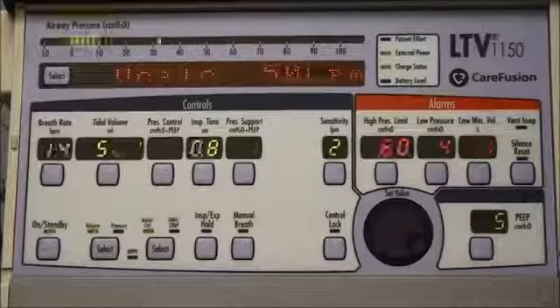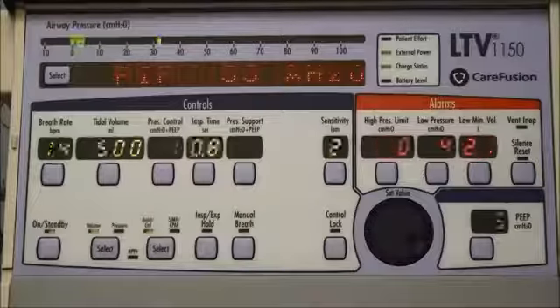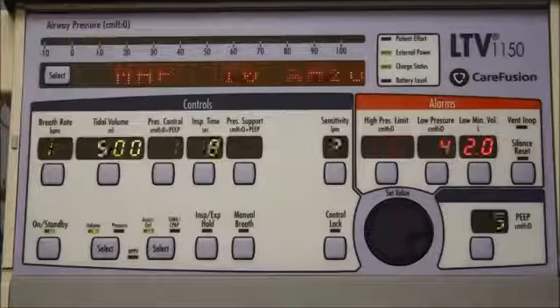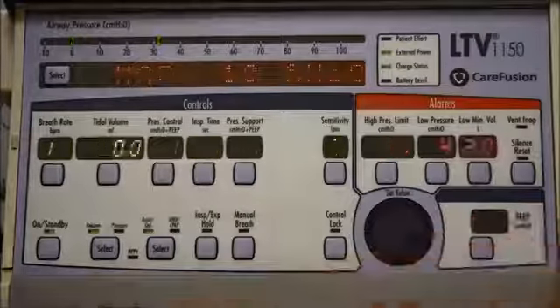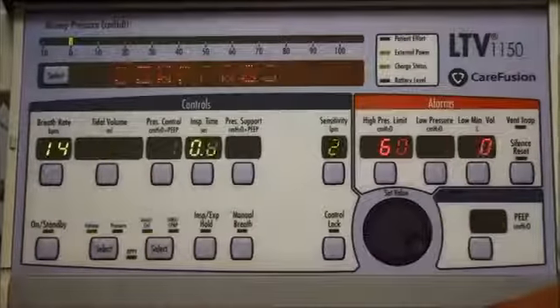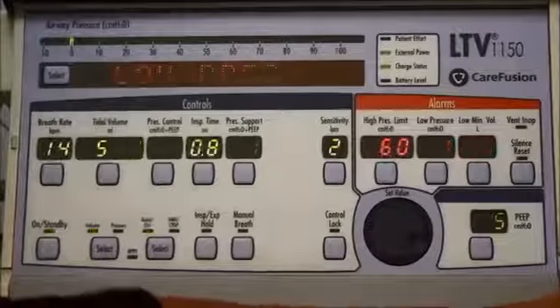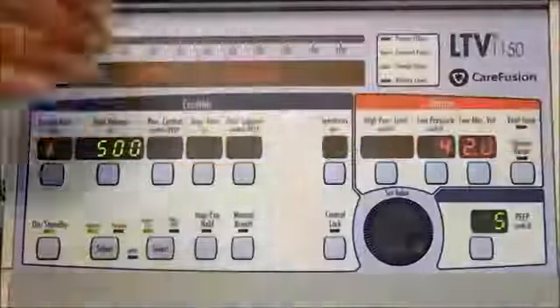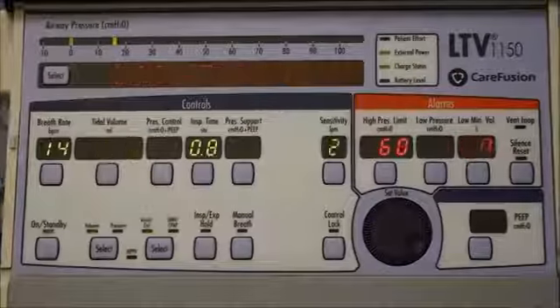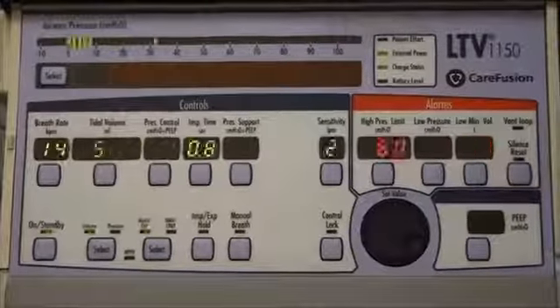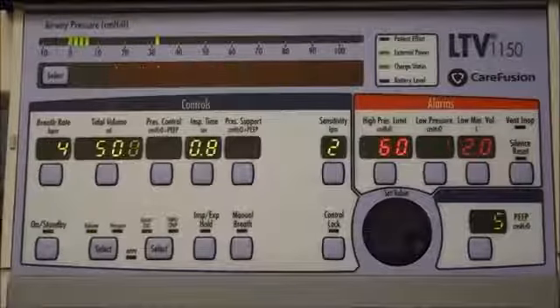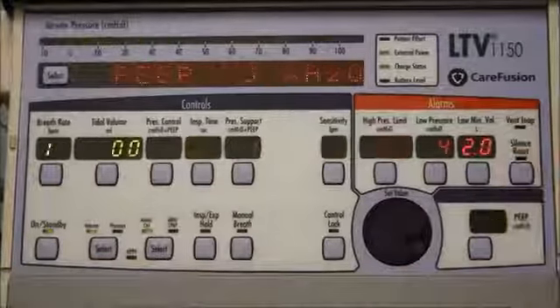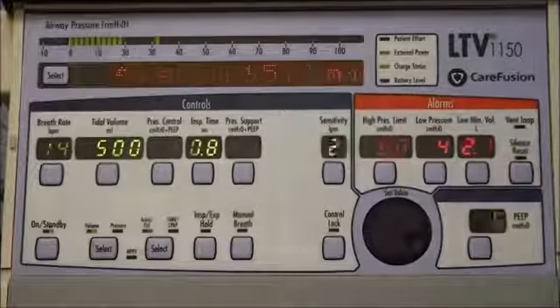You'll also notice that we got a disc sense alarm. And that's something that we talked about earlier. If one of your small tubings on the sides becomes disconnected, you can also get a low pressure disc sense alarm. Anytime I get a disc sense alarm, this would be the first place that I would check. So again, I'll just come and reset my alarms and we're good to go.